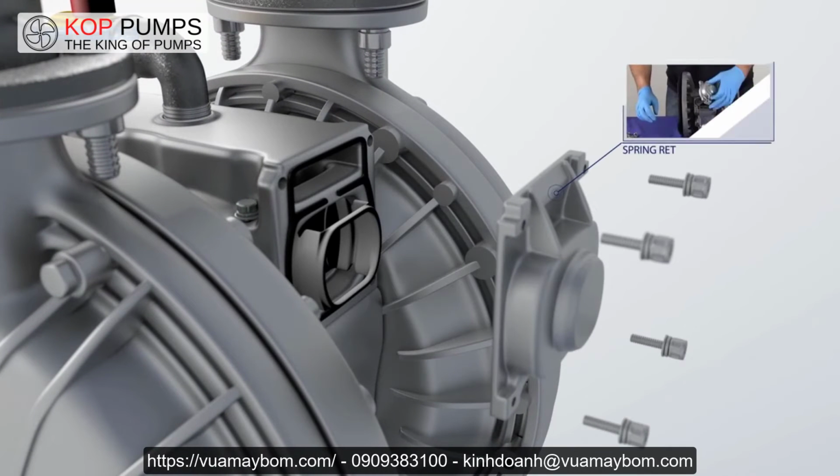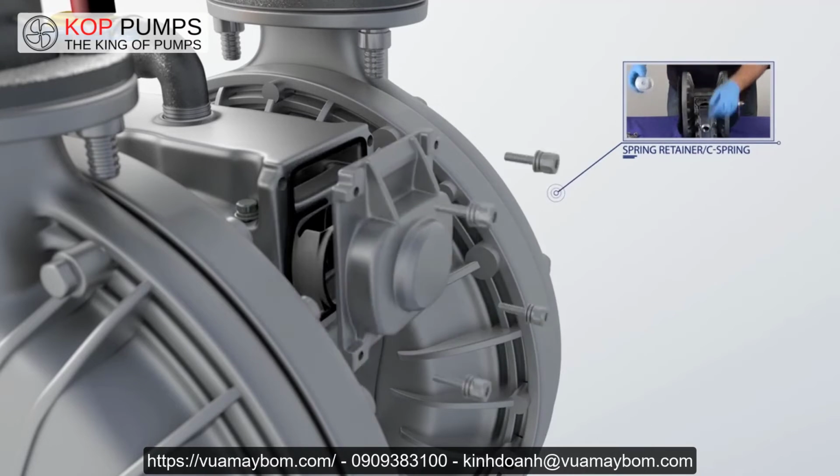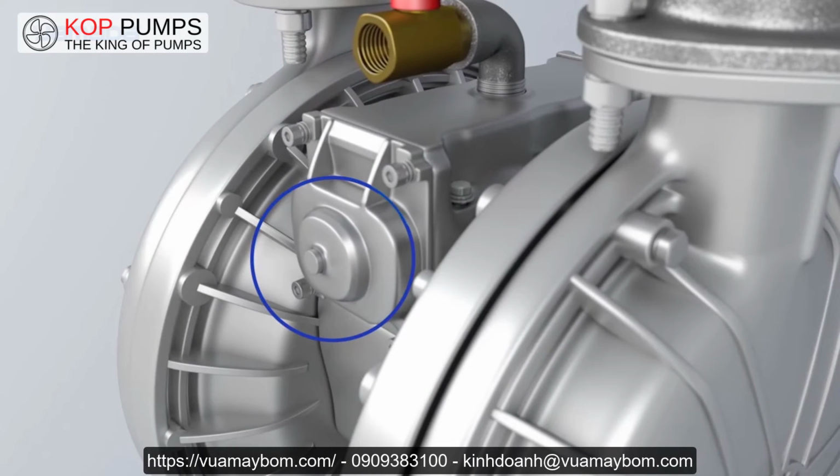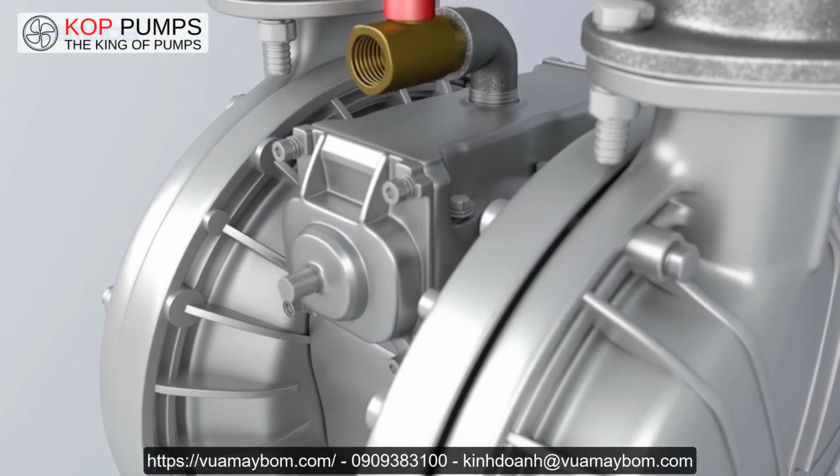Each air valve also contains a C-spring, helping to ensure a positive shift every time. Lastly, in the event that a stall ever does occur, every Yamada air valve has a maintenance indicator reset button. Depressing the button will shift the valve to one side, forcing the pump to reset and start pumping.